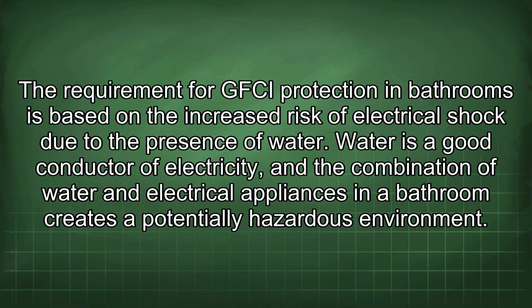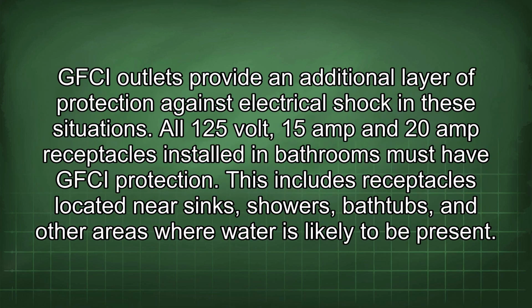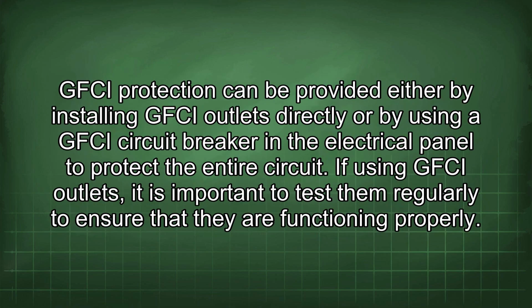Water is a good conductor of electricity, and the combination of water and electrical appliances in a bathroom creates a potentially hazardous environment. GFCI outlets provide an additional layer of protection against electrical shock in these situations. All 125-volt, 15-amp and 20-amp receptacles installed in bathrooms must have GFCI protection. This includes receptacles located near sinks, showers, bathtubs, and other areas where water is likely to be present. GFCI protection can be provided either by installing GFCI outlets directly or by using a GFCI circuit breaker in the electrical panel to protect the entire circuit.